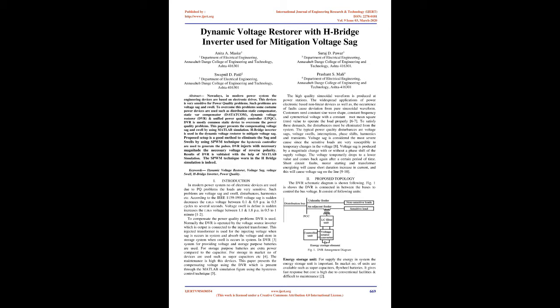To overcome this problem, some custom power devices are used, such as distribution static compensator, static VAR compensator, D-STATCOM, dynamic voltage restorer, DVR, and unified power quality controller, UPQC. DVR is the most common static device to overcome the power quality problems. This paper presents compensating voltage sag and swell by using MATLAB simulation. An H-bridge inverter is used in the dynamic voltage restorer to mitigate voltage sag.